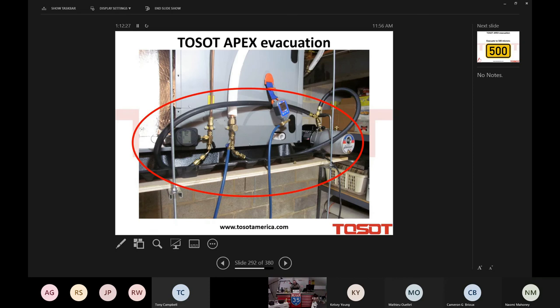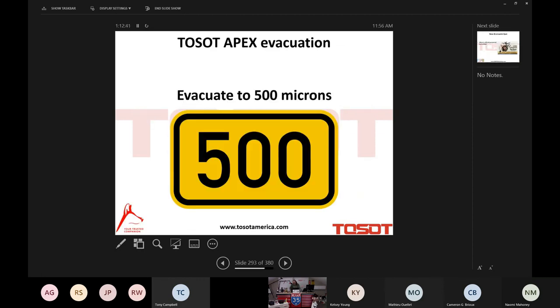And there you can see the entire kit in use, and it cuts down evacuation. Listen to me now. This is a strong statement. It cuts evacuation time down by 50%. Beautiful thing. We want to evacuate down to 500 microns. Lower is better, but all TOSOT is looking for is 500 microns.